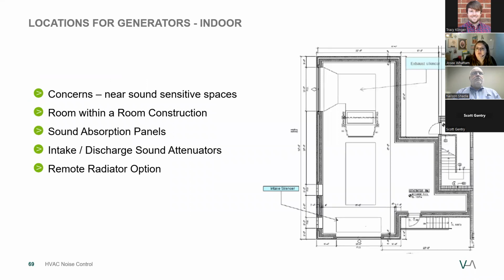Like I mentioned earlier, the location of a generator affects everything around it. The concern is for the occupied or noise sensitive spaces beside the generator room. A possible solution is a room within a room construction. This can include air gaps in all facets of the room, like between the walls, under the floor, and in the ceiling. Otherwise, sound absorption panels can be used on all surfaces within the generator room.